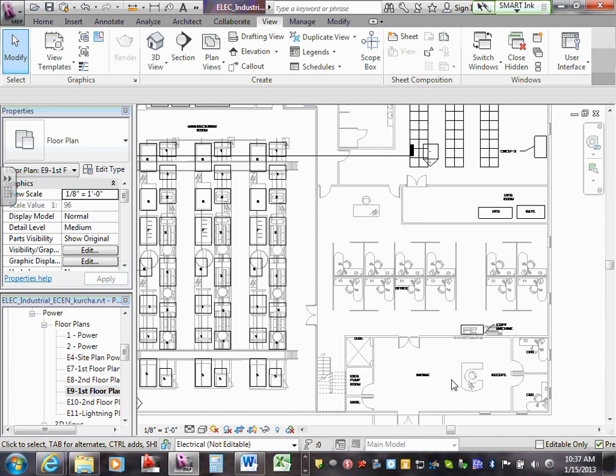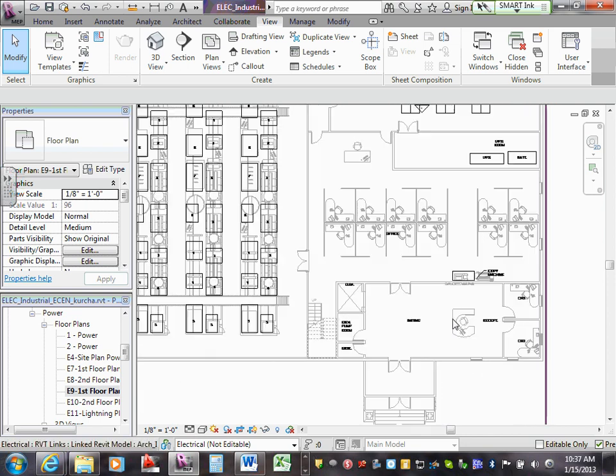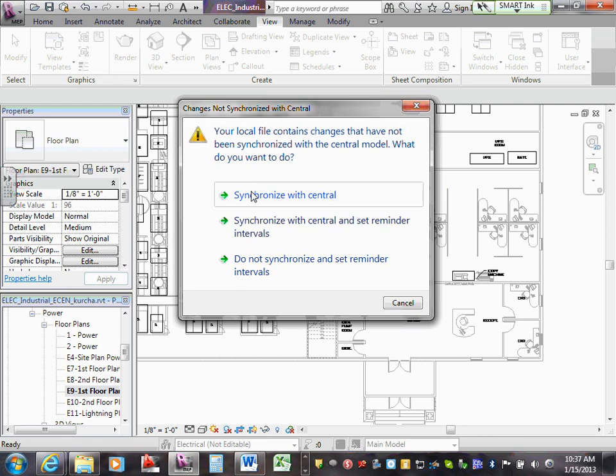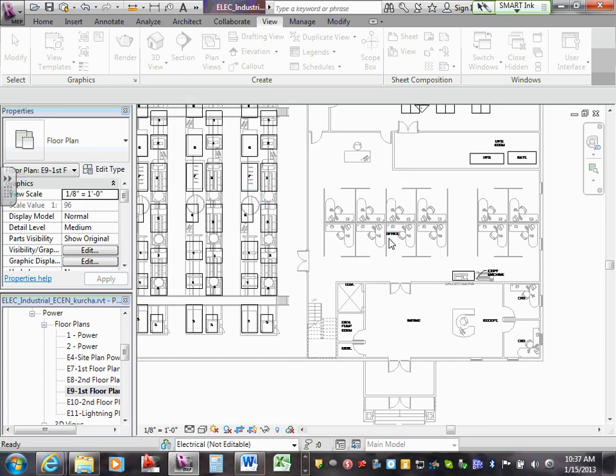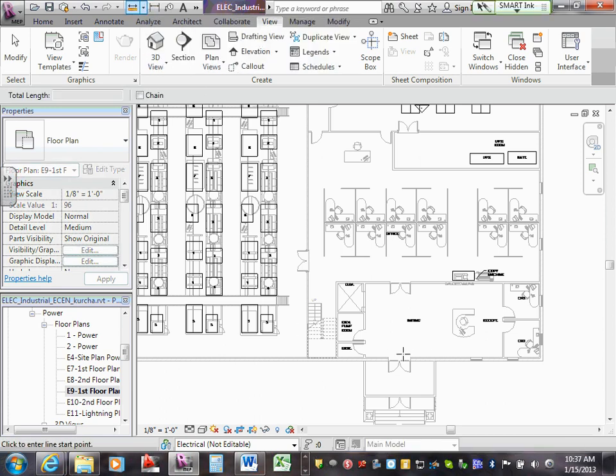So same thing in the lobby here. So you're gonna have one within 15 feet of that doorway, one side typically. I'm just trying to see what the distance is here, what the dimensions are. Yeah, right there, 37 feet. So you should be able to cover 19 by 37 with one in the central area. The way I look at it, if it's 50 feet in between, then I'll just put one on each side. That'll cover you, because 50 feet is your coverage, 50 by 50. So you're covered in here, you've got your office area covered.